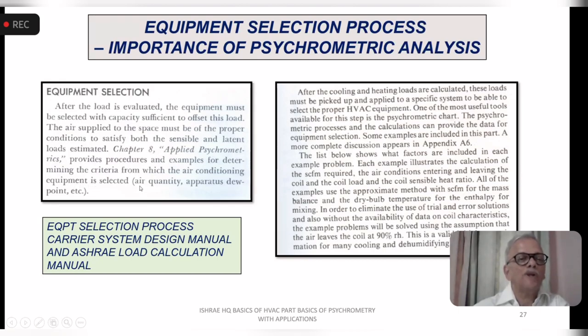So the air conditioning equipment parameters will be air quantity, apparatus dew point, etc. Air quantity, or the airflow rate, or the CFM, or the meter cube per hour of the air handling unit, and the apparatus dew point. We have learned about the dew point. This is the temperature at which the moisture in the air starts condensing. That is the surface temperature. So the apparatus has to be maintained at that dew point temperature, and we will see further how the apparatus dew point is checked or calculated. So that is the Carrier system method.